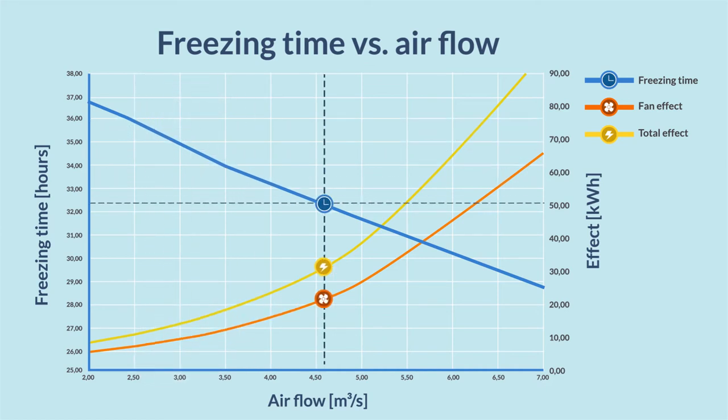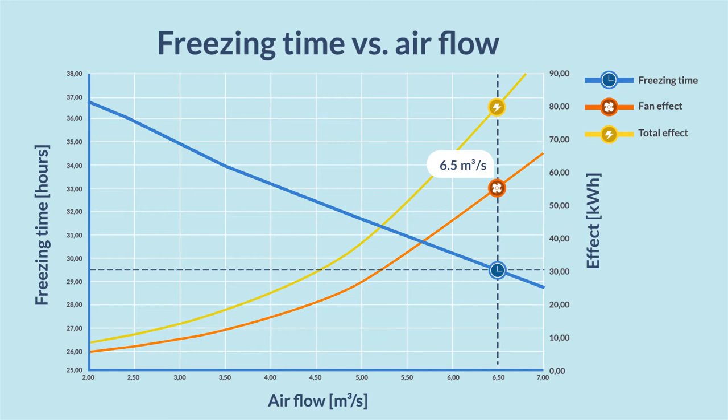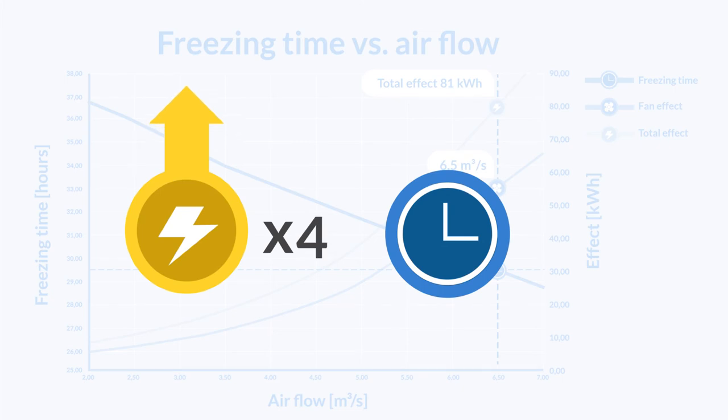When increasing air flow to 6.5 cubic meters per second, the freezing time shortened from 36 hours to 29.5. However, the energy consumption increased to 81 kilowatt-hours, a shocking seven-fold increase, just to reduce the freezing time by 6.5 hours, or less than 20%.